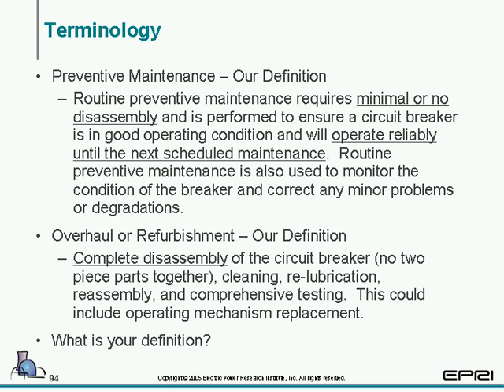Just some terminology. Preventative maintenance, our definition, yours may be different, but our definition is routine preventative maintenance requires minimal or no disassembly and is performed to ensure a circuit breaker is in good operating condition and will operate reliably until the next scheduled maintenance. Routine PM is also used to monitor the condition of the breaker and correct any minor problems or degradations. Definition of overhaul and refurbishment, as we see it, is complete disassembly of the circuit breaker, that is, no two-piece parts together, cleaning of all parts, relubrication as needed, reassembly, and comprehensive testing.